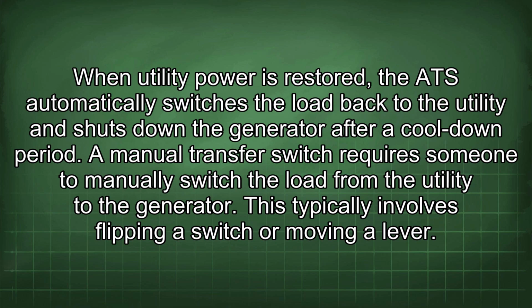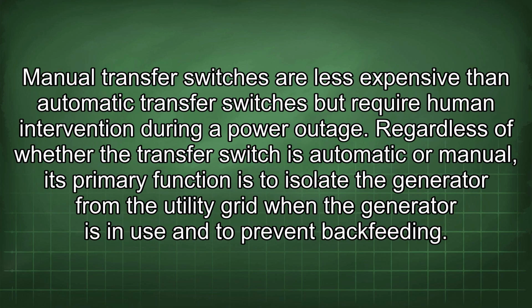A manual transfer switch requires someone to manually switch the load from the utility to the generator. This typically involves flipping a switch or moving a lever. Manual transfer switches are less expensive than automatic transfer switches but require human intervention during a power outage. Regardless of whether the transfer switch is automatic or manual, its primary function is to isolate the generator from the utility grid when the generator is in use and to prevent backfeeding.